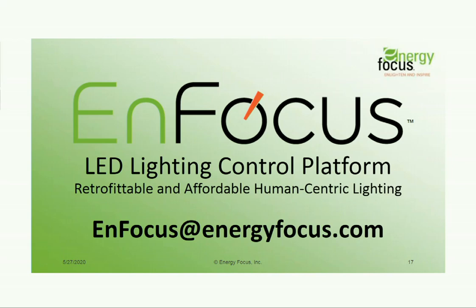Great. And on a technical side, how many fixtures can I put on one switch? A lot is the short answer. For example, if you have a school that has a 277 volt installation, in fact, you don't have many options with 277 volts. But if you have a 277 volt installation, which is common, you could put in more than 20 fixtures, with a typical distribution of bulbs. That's a room full. That absolutely is a room full. Typically you won't see that many. Typically you start seeing multiple switches and what have you. But yeah, absolutely, 20 is quite a bit. I like the concise answer of a lot. That's great, John.